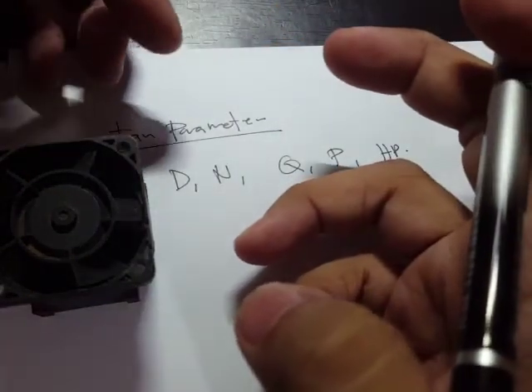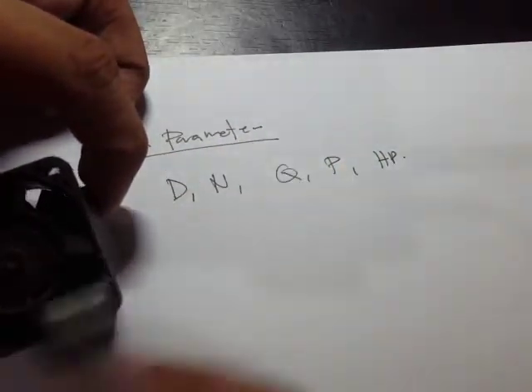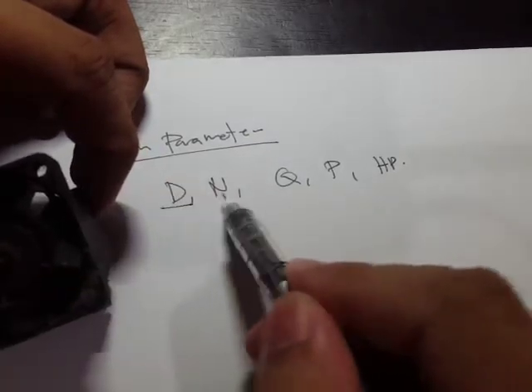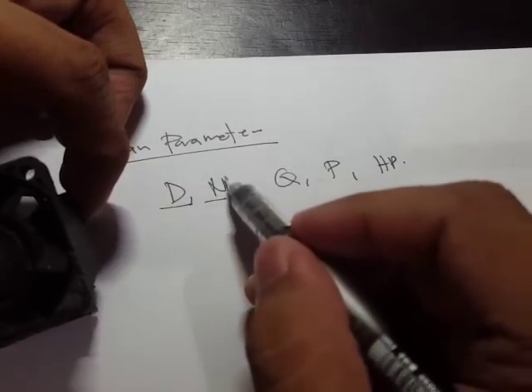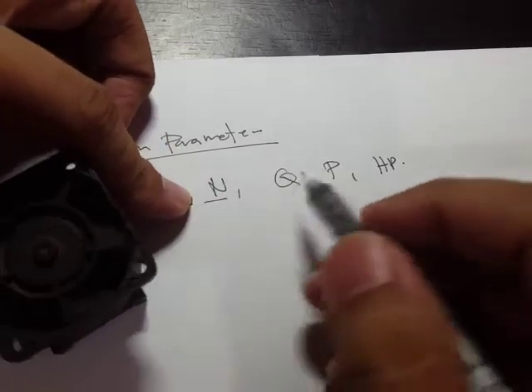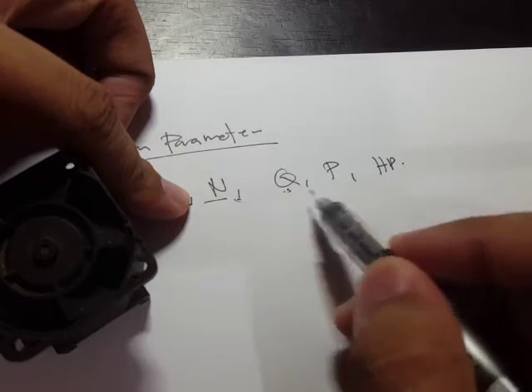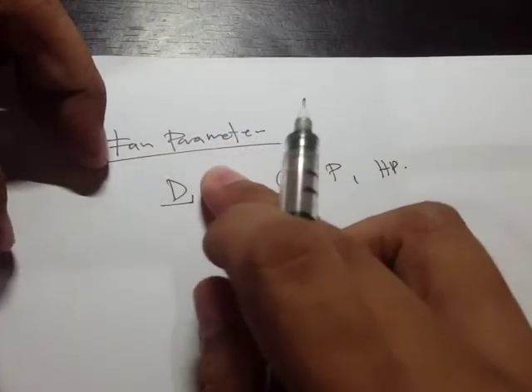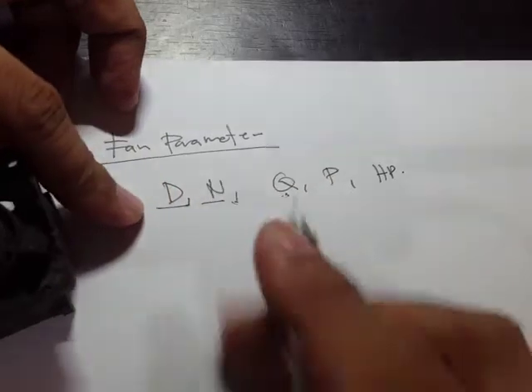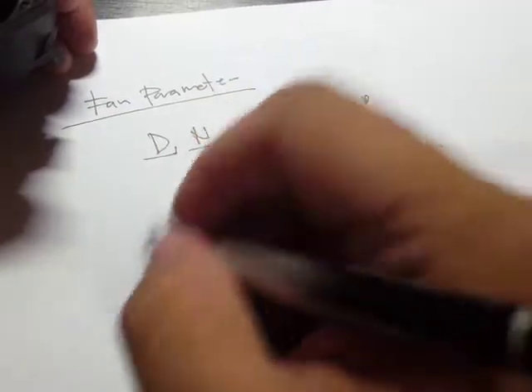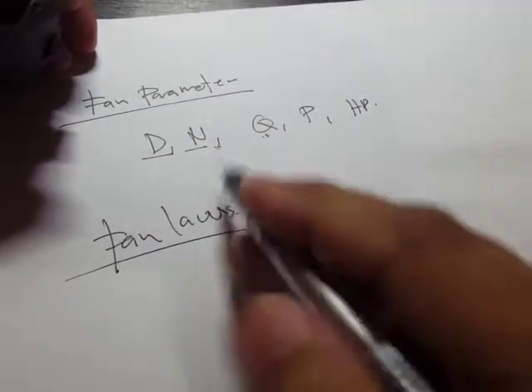For example, if we have a larger diameter fan, it will have a different performance. Or if we have this diameter and I double the speed, the flow rate will also double. So basically, if we change the speed while holding the diameter constant, what's going to be the effect on the flow rate, the pressure, and the horsepower? Or if we hold speed constant and change the diameter — make it larger — what's the effect on flow rate, pressure, and horsepower? That's essentially what fan laws describe.